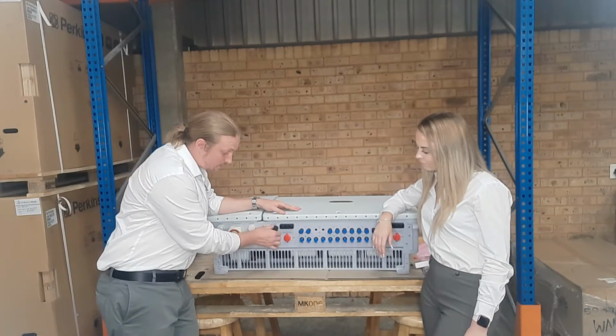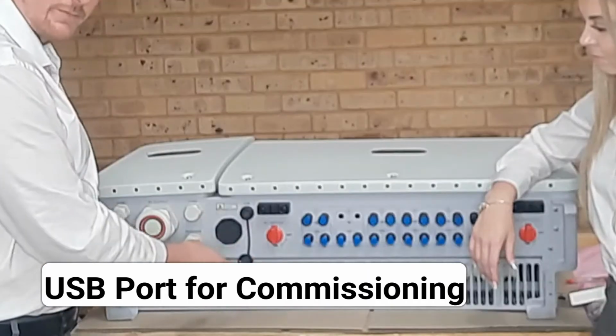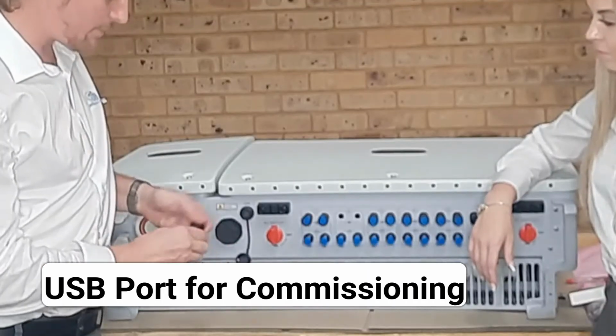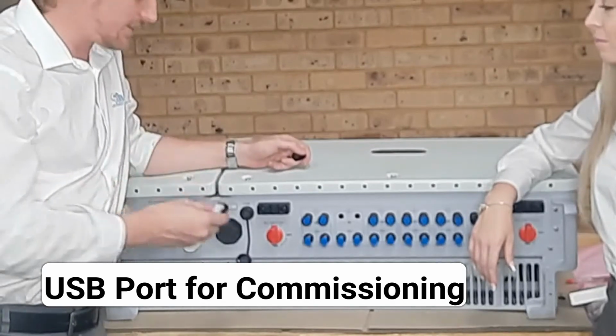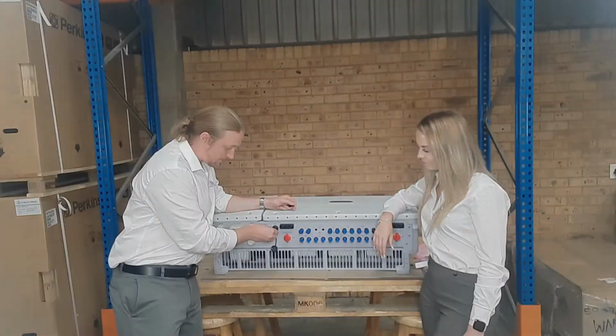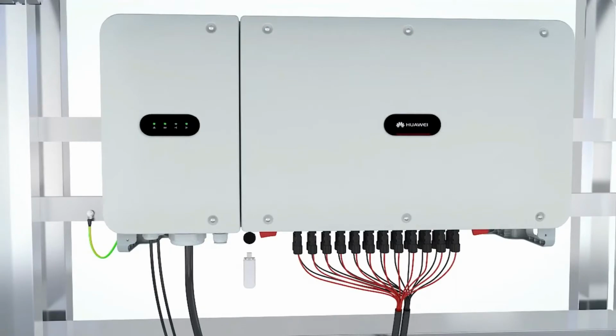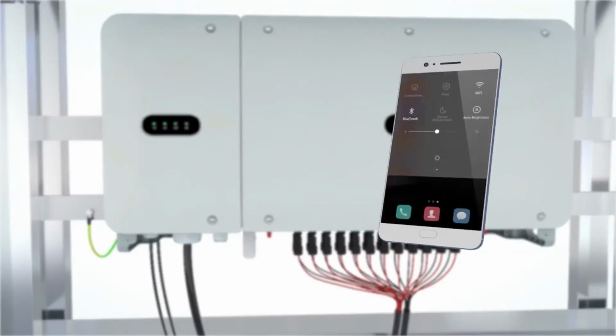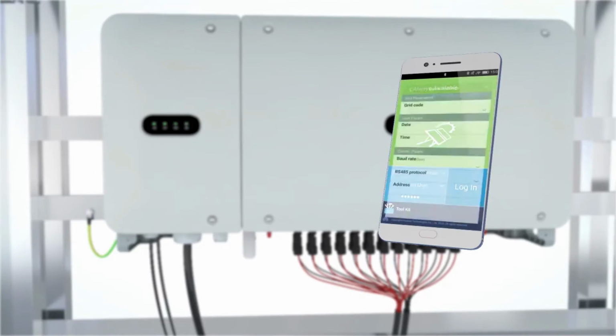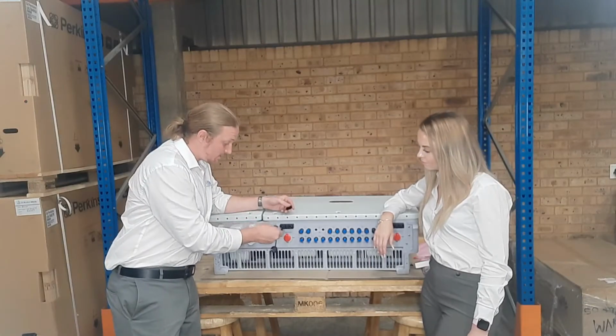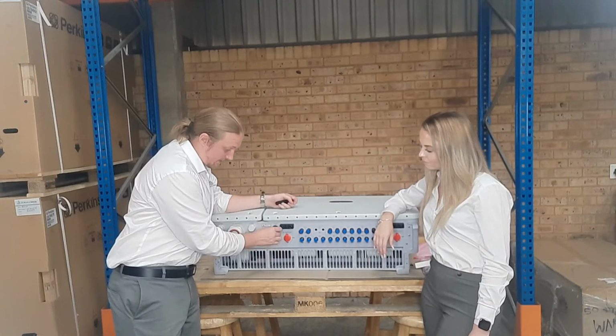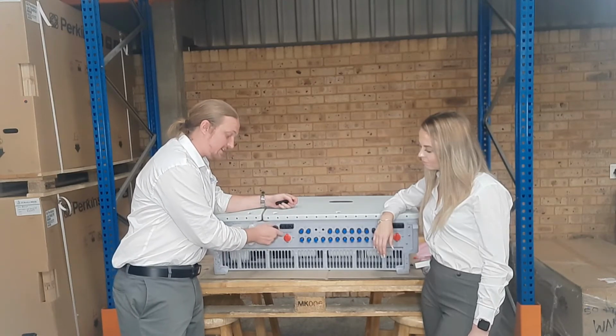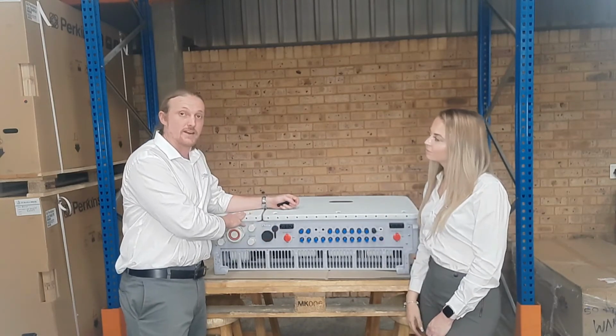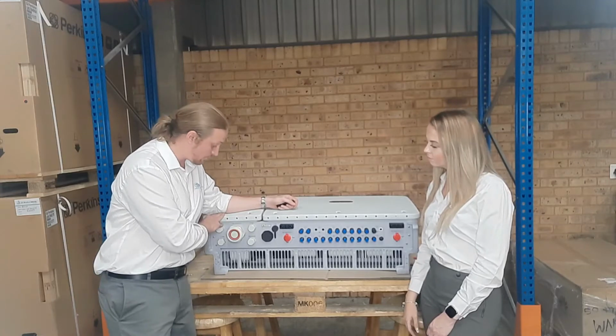Here we have a USB port that is used during commissioning. Simply unscrew the cap. Now you can insert this USB stick that comes with the inverter. This will create a short-range Wi-Fi signal so you can connect your laptop or smartphone and set the parameters of your inverter. Once you've done that, you can remove the USB stick and return the screw cap so that it keeps its IP65 rating, which means it's waterproof and dustproof.